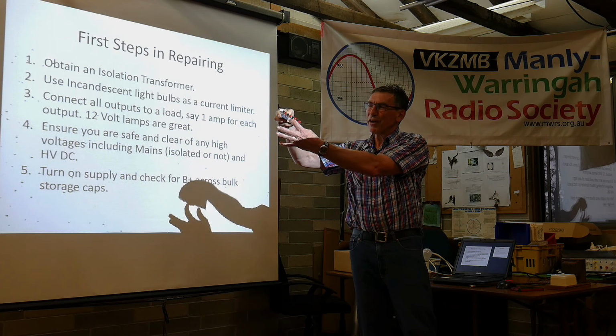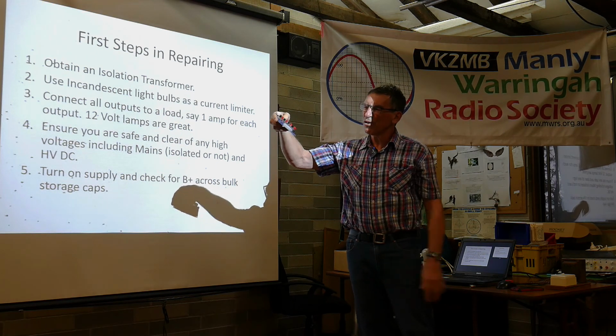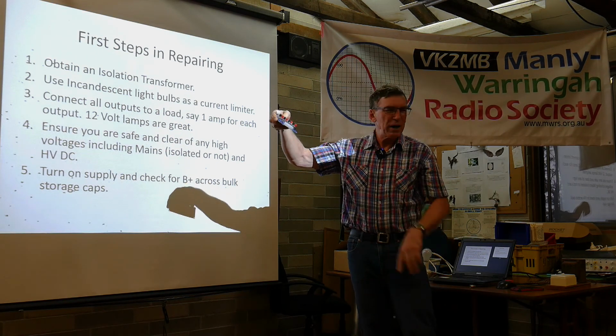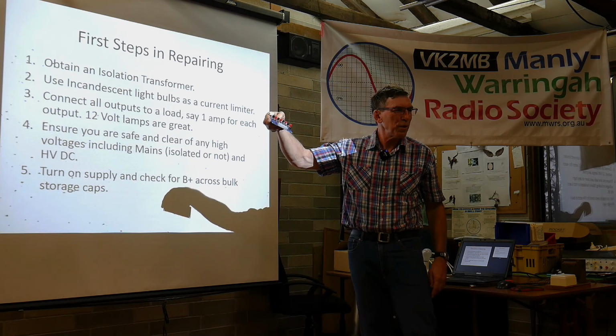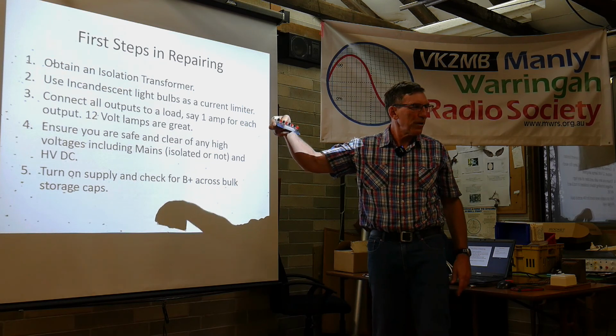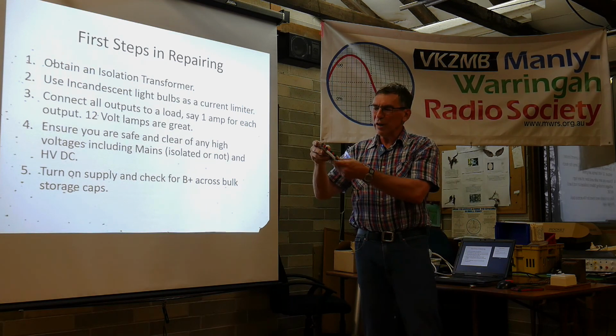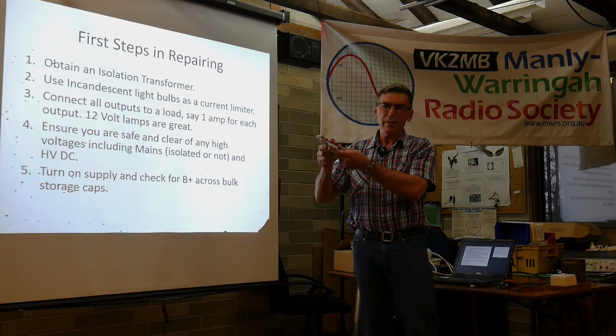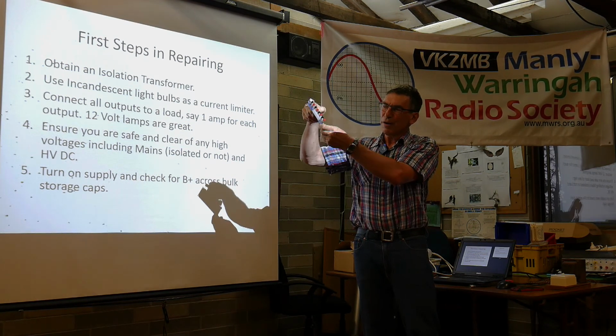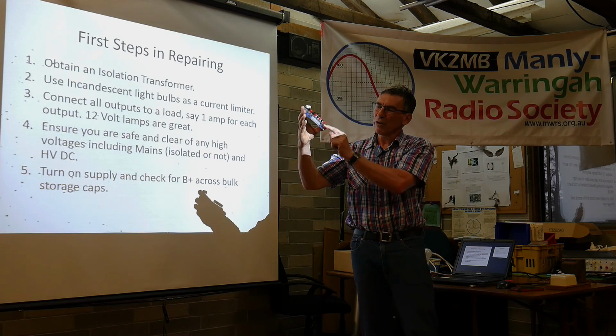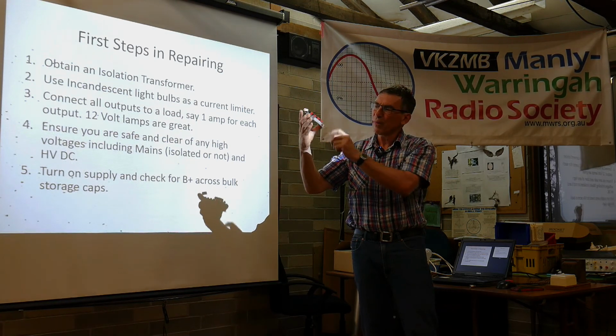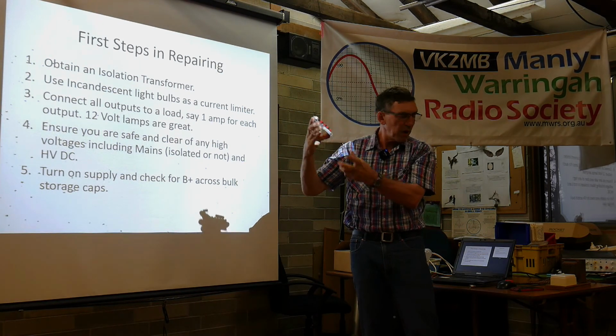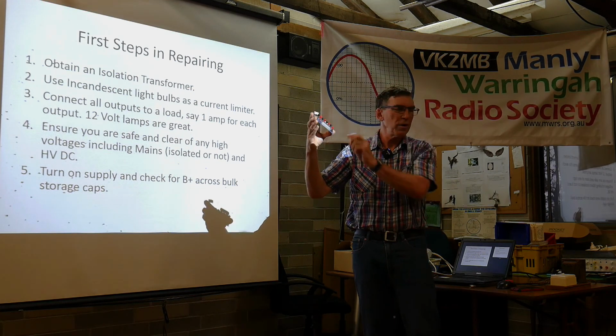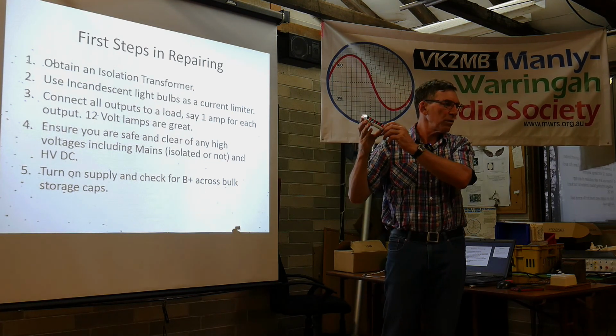You can plug your ATX connector in there, and it's got an on-off switch. It's not the bee's knees because the fuses are all about 1 or 2 amps, and the supply is supposed to be doing 40 amps or so on some of the outputs. But it's good enough to load it down, at least get the measurements. It breaks out all the different voltages, and you've got a little switch there to turn the thing on and off, because there's a green wire through here which plugs in from the supply that de-earths it, and everything should come on when you turn that on.